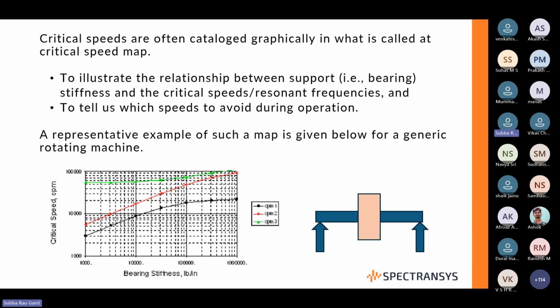There is no ISO standard, but if you refer to most API standards, American Petroleum Institute standards, when you're trying to buy a steam turbine, gas turbine, centrifugal compressor, pump, or anything like that, they specify that it should be less than 10 or 15 microns.